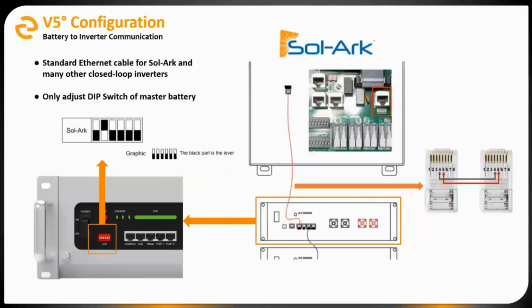Once we've taken care of battery to battery communications, next you'll want to look at battery to inverter communications. Again, my example here has a Sol-Ark, but the process is pretty similar. You're going to make sure you have a communications cable connected from the master battery to the battery COM port on your inverter. Sometimes that cable can be a special modified communication cable with some of the pins being crossed over. In the case of Sol-Ark, specifically, they just use a standard Cat5 or standard Ethernet cable. So we don't have to worry about any custom cables with Sol-Ark.